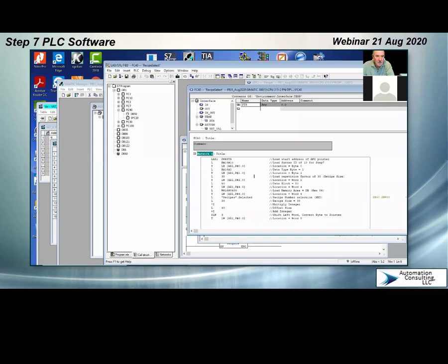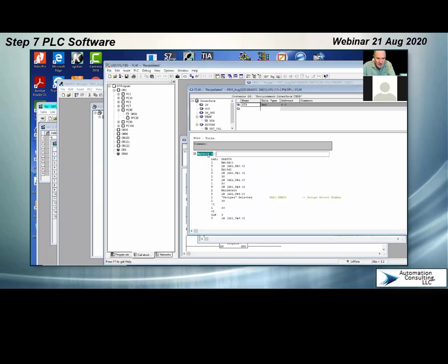Now, if you're familiar with Allen Bradley, it allows you to do this within an array. You can simply put a square bracket and then put a number in the square bracket, and it will move whatever you pick up as an array element. I can move a whole UDT. TIA Portal in Siemens does the exact same thing. I can use an array and simply put the pointer in the square brackets. I don't have to build this kind of code. But in Step 7, this is pretty much your only option for building this structure.